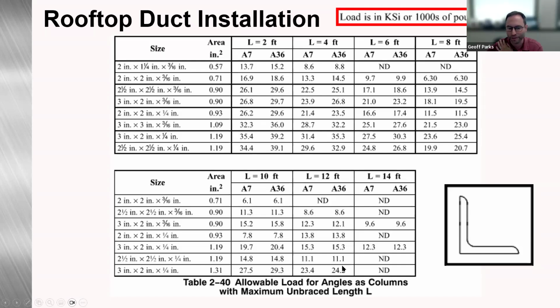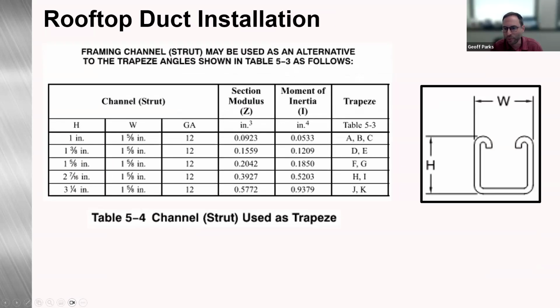So this chart, this table goes all the way up to 14 feet. A couple things to point out: the A7, A36, that's just your grade of steel, and then ND basically means not designed. And then a lot of people up on exterior rooftops like to use framing channel or strut. Table 5-4 is channel or strut that's used as trapeze. So if you go back to that table 5-3, size your angle for the trapeze, you can then come to this table and then get the alternative channel strut size required.